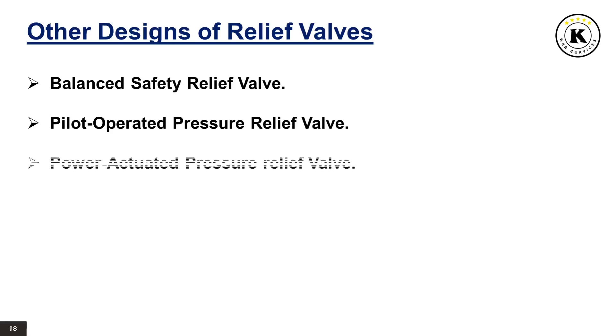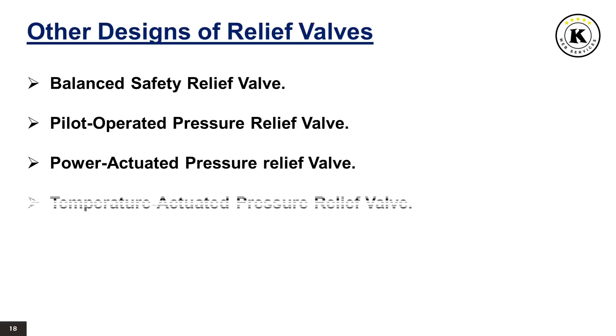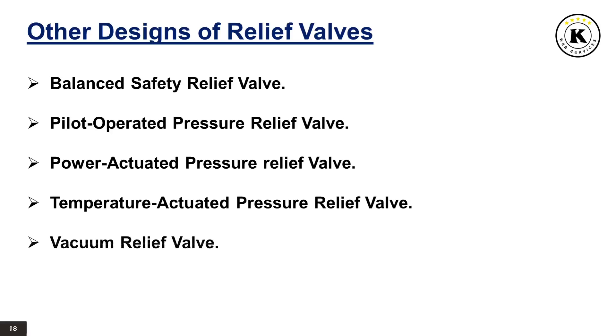Power Actuated Pressure Relief Valve: a power actuated pressure relief valve is a pressure relief valve in which the major relieving device is combined with and controlled by a device requiring an external source of energy. Temperature Actuated Pressure Relief Valve: a temperature actuated pressure relief valve is a pressure relief valve which may be actuated by external or internal temperature or by pressure on the inlet side. Vacuum relief valve: a pressure relief device designed to admit fluid to prevent an excessive internal vacuum, designed to reclose and prevent further flow of fluid after normal conditions have been restored.